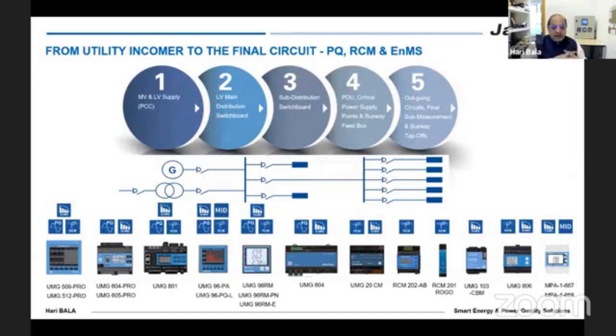Say, for example, in one case in the Middle East, a customer, after 3 years of using the facility, wanted a particular power factor trend. Then they realized the meter did not have power factor itself. So it was very difficult for them to understand the power factor when they had operated the plant without noticing the power factor as a parameter. But when they wanted the data afterwards, they didn't have it, because they had the same kind of meter all through their network, which becomes complex for them to understand their own systems. So the point I wanted to take across is that every point in your network requires a different set of meters according to what you want to monitor, and different places have to be with different values. That will help the customer very effectively in the long run.